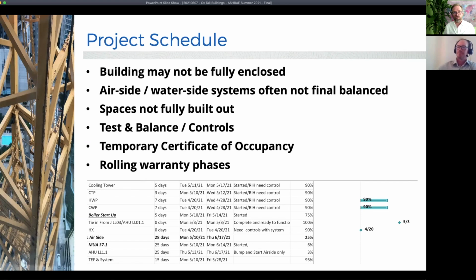And also when it comes to the schedule with all the moving parts, a lot of things can get neglected or maybe not even done up to the correct standard, especially when it comes to airside and waterside systems and the balancing of those systems. When we do a multifamily residential building and we're looking at the airside systems, we'll have toilet exhaust risers, kitchen exhaust risers, dryer risers for exhaust, and makeup air units bringing fresh air to replace that air and to help manage some of the pressurization and stack effect. When the building's not fully enclosed or systems aren't quite balanced, you're kind of beating your head against the wall, testing things at this early phase. You're maybe finding some functional issues, but you're not really getting the whole building as it's going to live and breathe. You want to make sure that you plan out your schedule with the contractor's schedule to make sure that you're able to test these things when it's ideal and it's the best possible time.